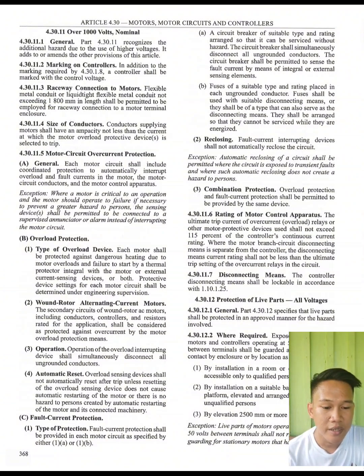So A, a circuit breaker of suitable type and rating arranged so that it can be serviced without hazard. The circuit breaker shall simultaneously disconnect all ungrounded conductors. The circuit breaker shall be permitted to sense the fault current by means of integral or external sensing elements. B, fuses of suitable type and rating placed in each ungrounded conductor. Fuses shall be used with suitable disconnecting means, or shall be of a type that can also serve as the disconnecting means. These shall be arranged so that they cannot be serviced while they are energized.